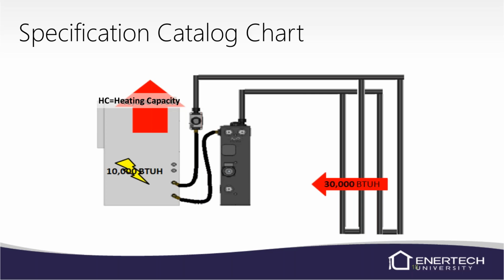There's a calculation for that, and that's volts times amps times the efficiency of your compressor equals watts. So volts times amps equals watts. If we were to take 240 volts times 15 amps, and multiply that times a correction factor. Normally a compressor is about 90 to 95% efficient. So we take that number from our amps times our volts, and I usually use 0.9 because it's easy, which is 90%. And then that'll give you a number, and that's going to be the amount of BTUs that you're going to add to your extraction for your total heating capacity.